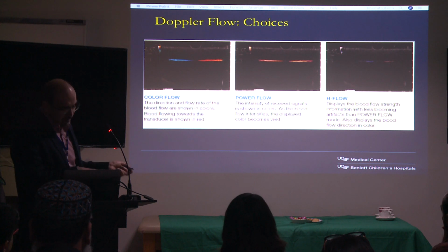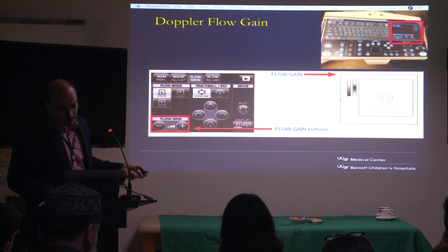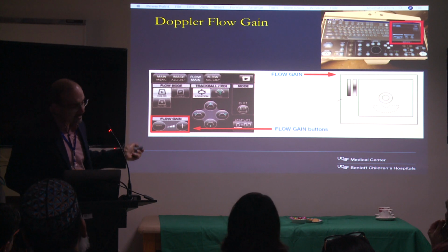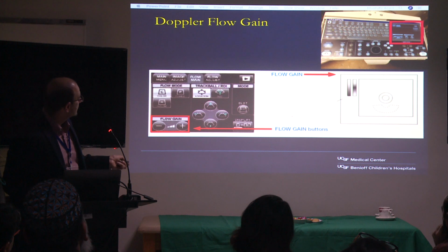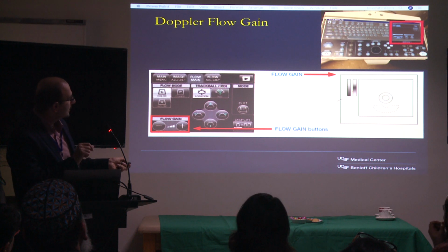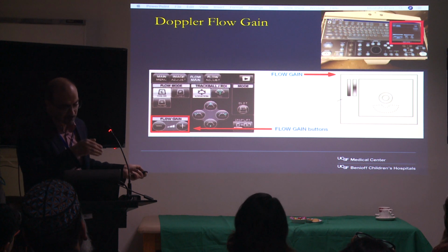And when you want to see, you can adjust the gain on the flow in your area of interest, to see if you're getting flow or not. It may be that you just need to increase the strength of the flow signal.